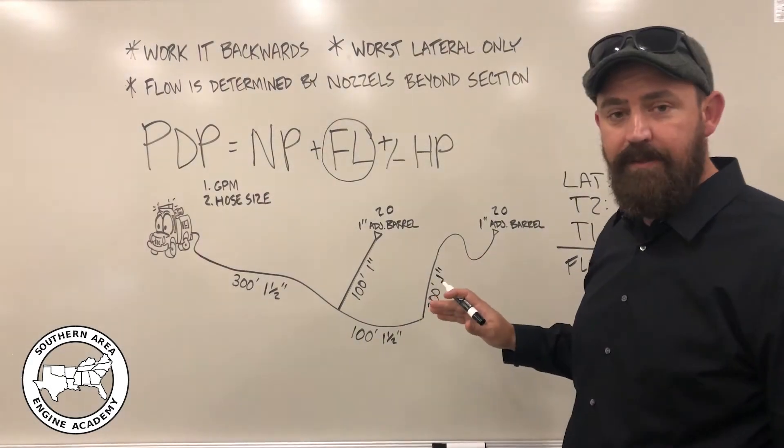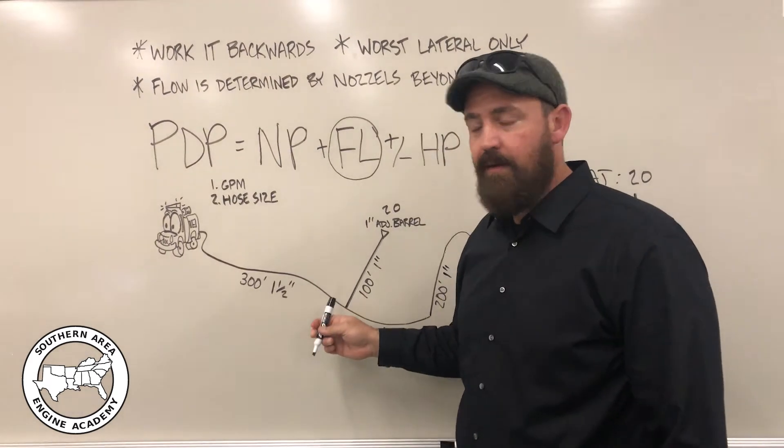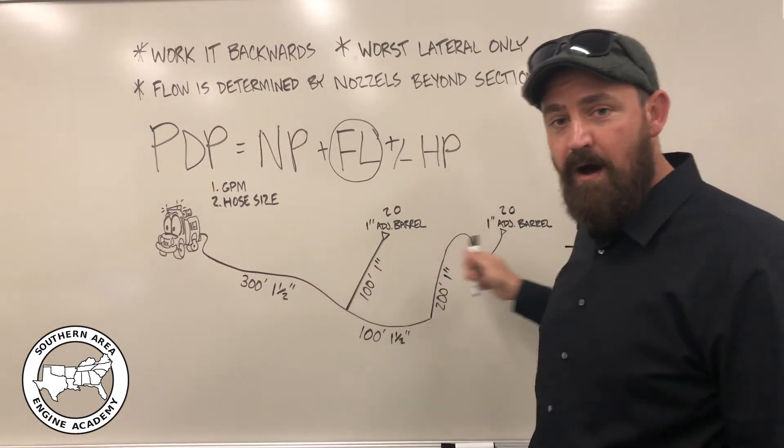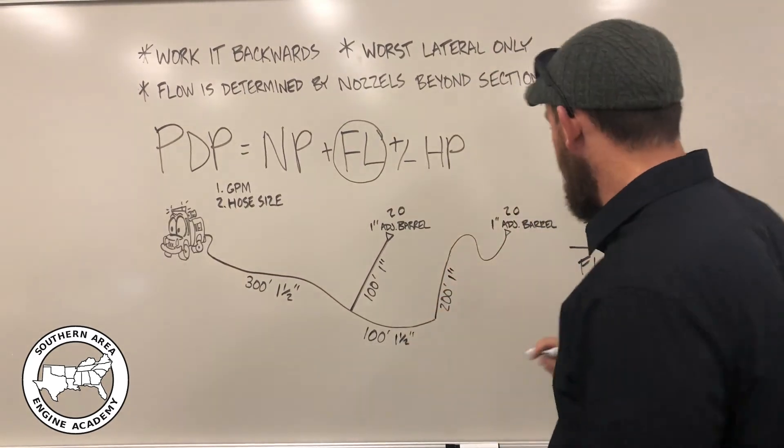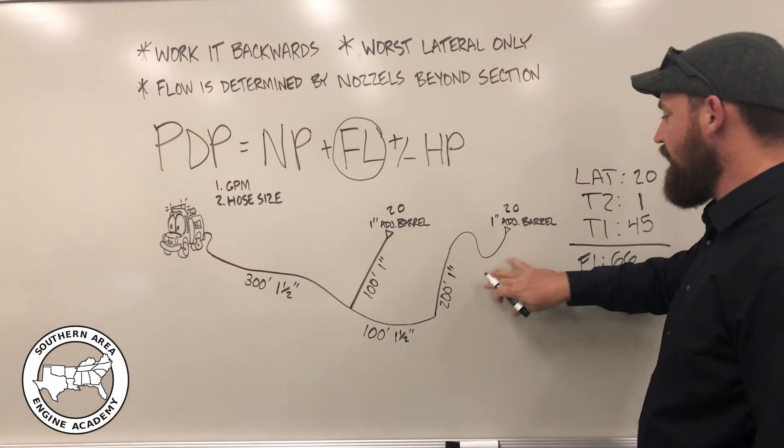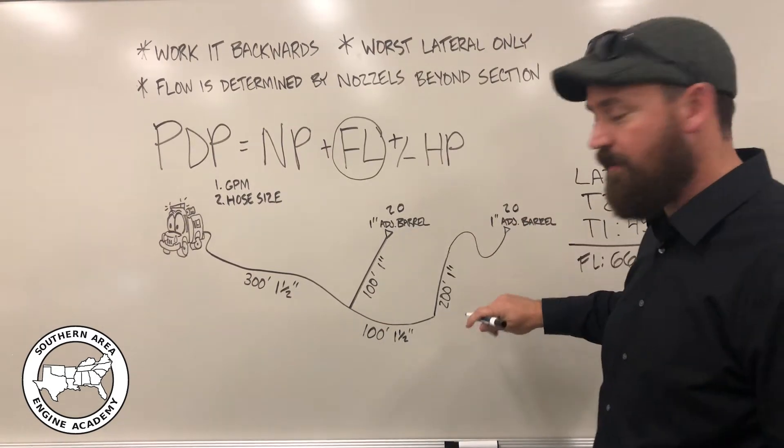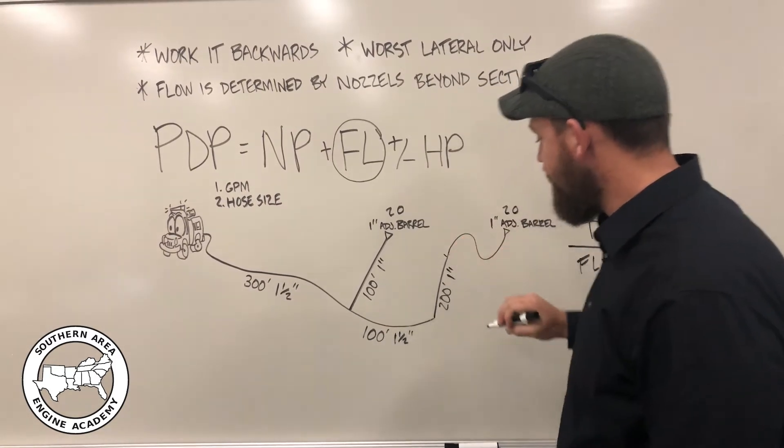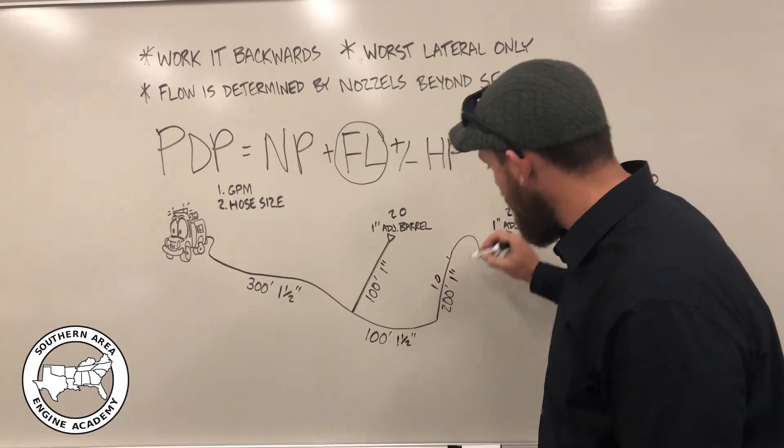So, our next rule of thumb is that the flow for each section is going to be determined by the nozzles that are beyond that point in the hose lay. So, as we've worked backwards, from our lateral here, we see we have 20 GPM of flow. So for each section of one-inch hose, that's 10 PSI of friction loss.